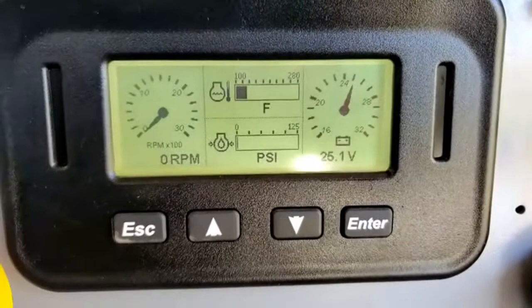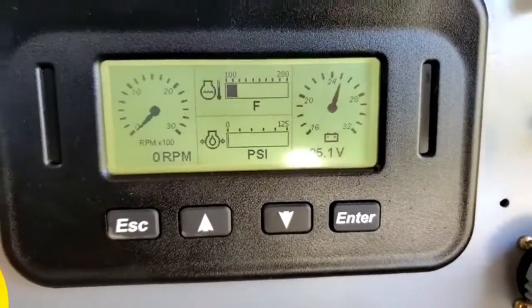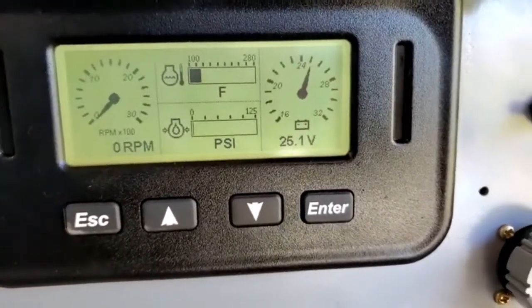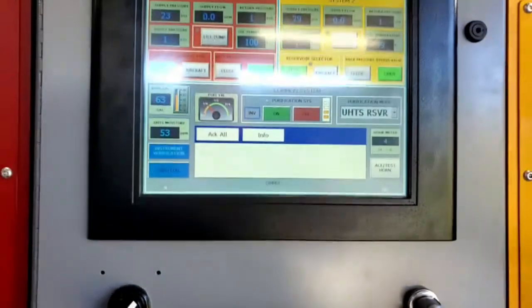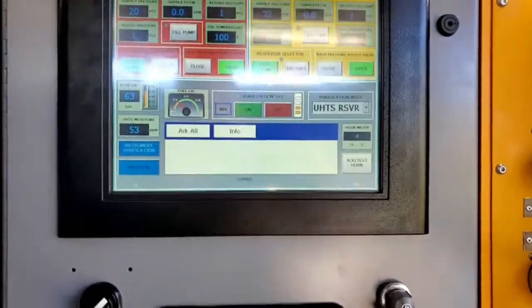Make sure your voltage is well over 24 volts. The unit can start down to 20 volts. It's possible that the HMI could kick off, but it should reboot as soon as the engine's running on alternator power.